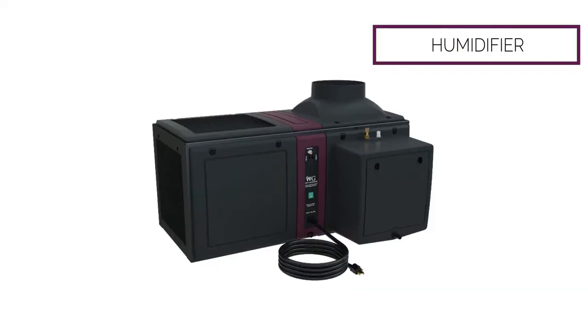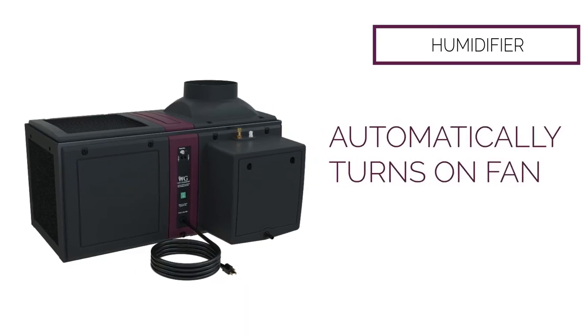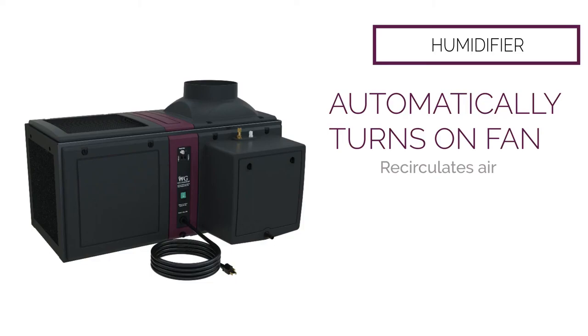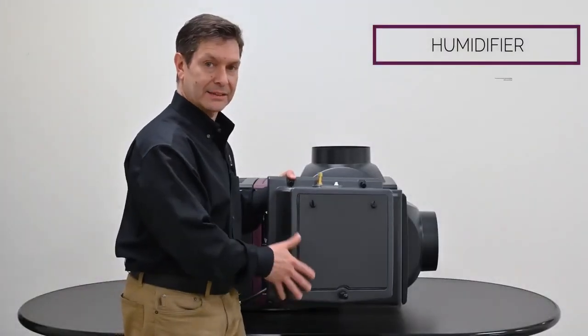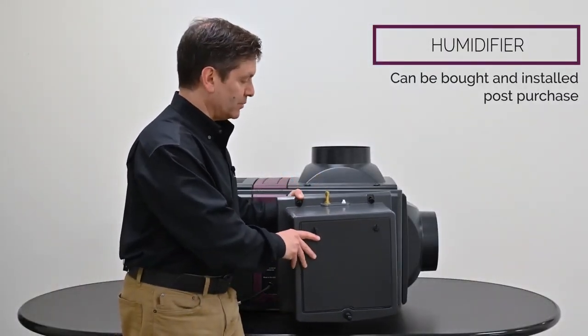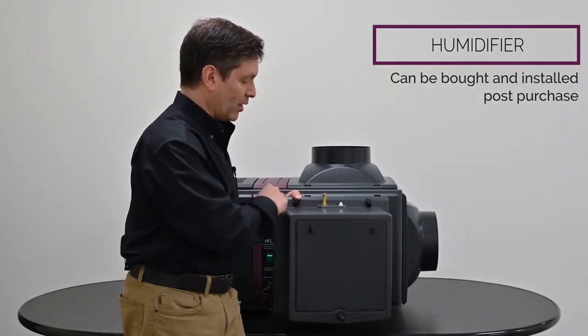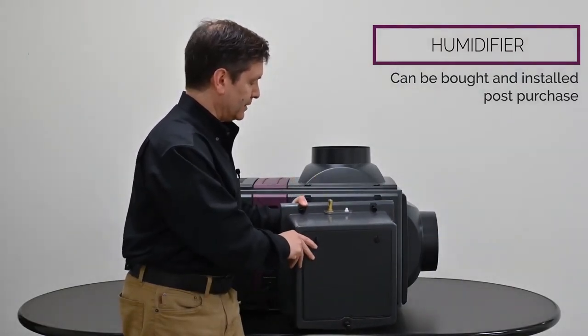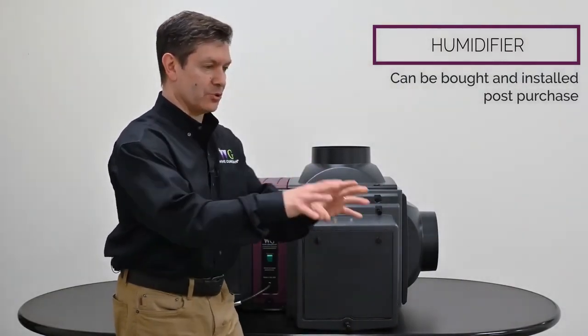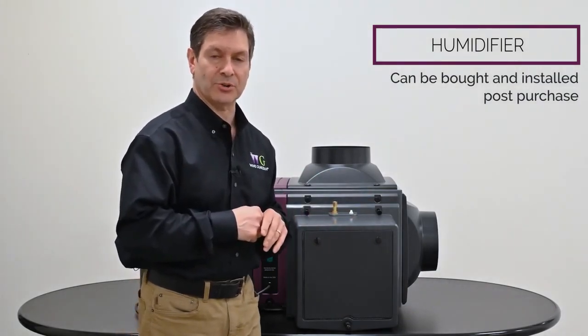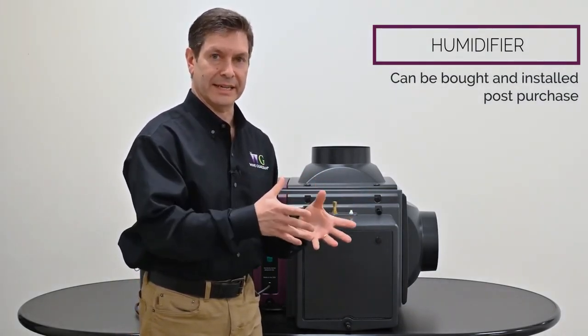In addition to that, if temperature is satisfied in the wine room, the humidifier will automatically turn on the fan in the system to recirculate the air and humidify the wine room if it's too dry. So you can add this at a later date if you wanted to. Again, keep in mind you'll need a water connection, a drain line, and the controls. You'll need to set up our controller to understand that it has a humidifier connected to the device.